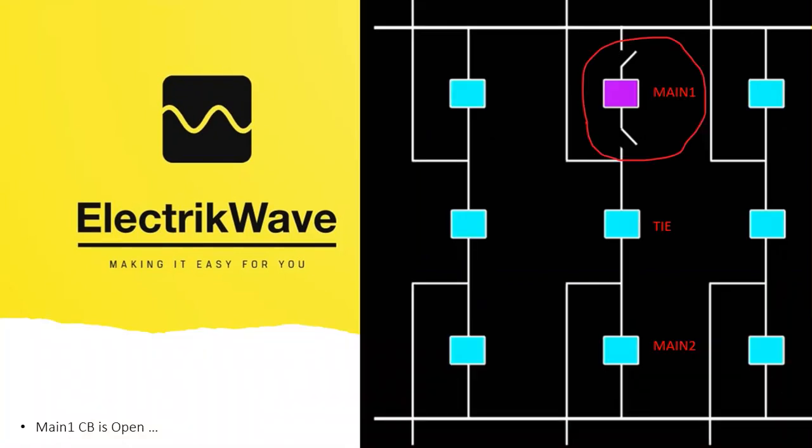A fault on any bus is cleared by the opening of the associated circuit breakers, without affecting continuity for supply. Similarly, any circuit breaker can be taken out for maintenance without causing interruption. All load transfer is done by the breakers and therefore, the operation is simple.